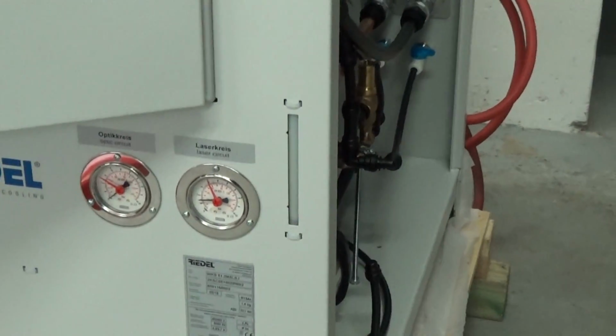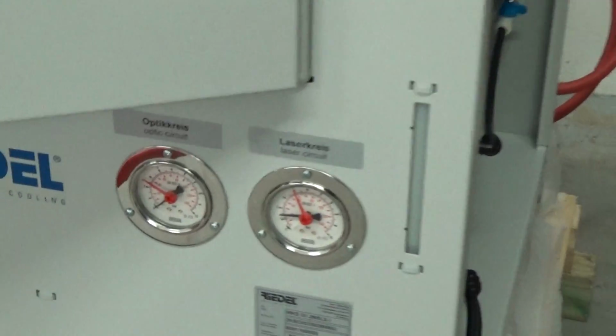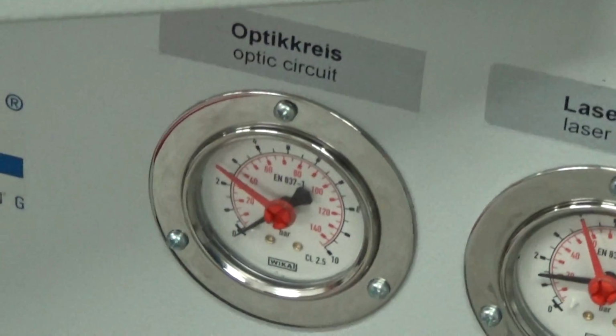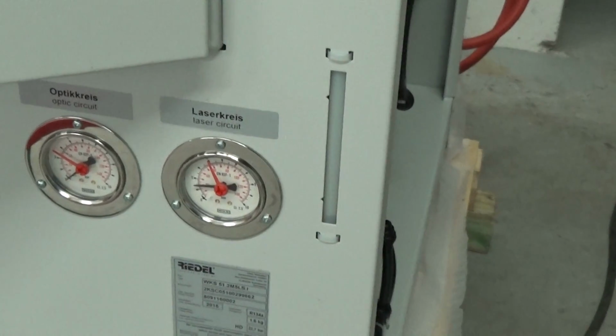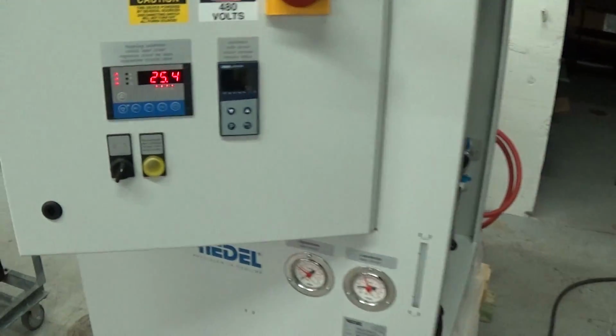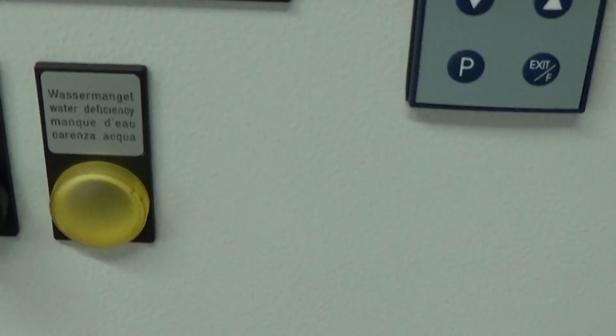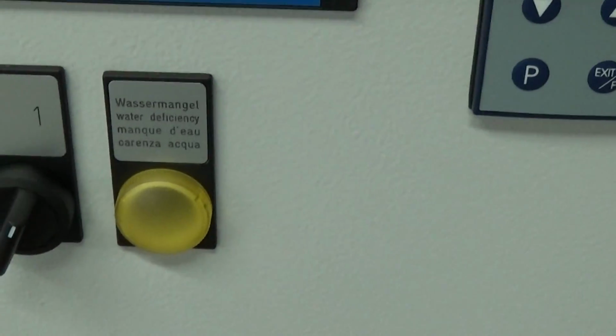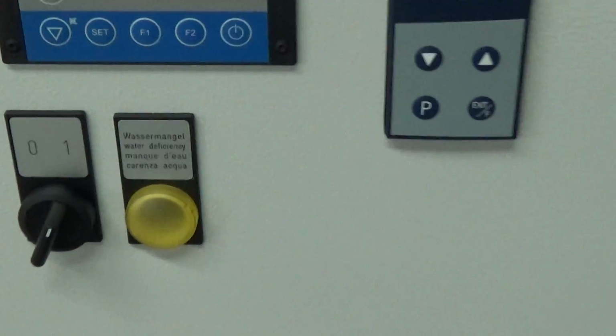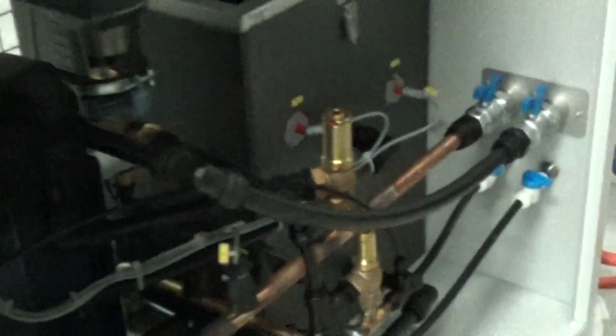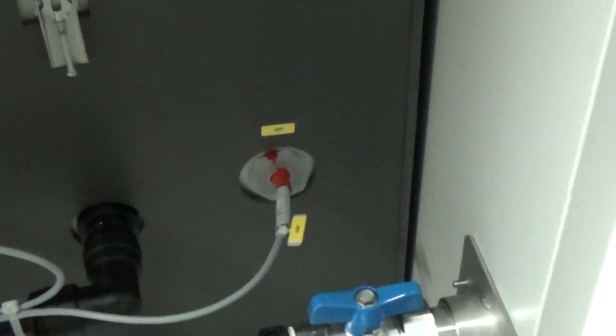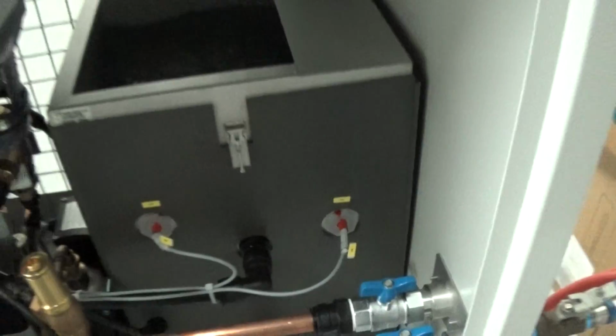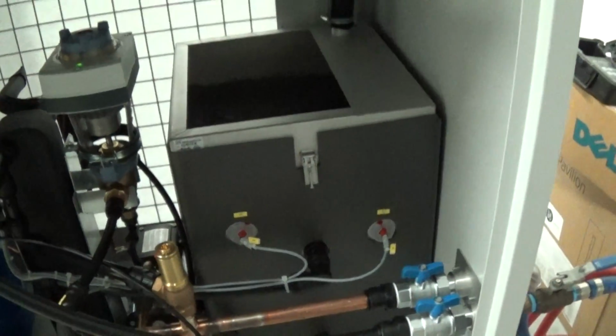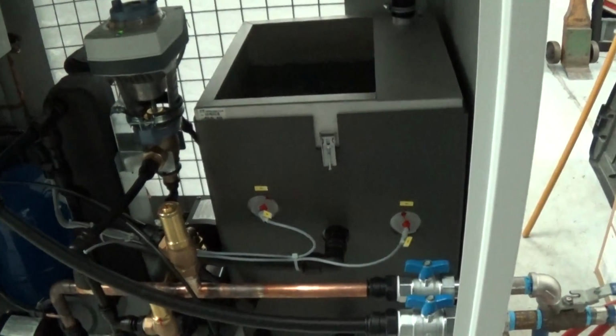We have a pump pressure gauge. It's in bar, but you're not going to see any pressure for what they call the optic circuit. We're just going to be using the laser circuit here. And this warning light here, water deficiency, I think they call it, that's just if the tank level goes down. There's actually 2 float switches in the tank, here and here. It's kind of nice. Usually we just see one. They just want to make sure it's in that happy medium.